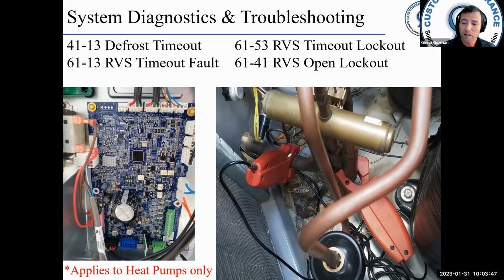Basically, you want to check the temperature difference across the valve, whether you're in cooling or heating. It's important to remember the single pipe on the reversing valve is always discharge, and the one in the middle of the 3 is always suction. What changes are the other 2 pipes. Whether you're in cooling or heating, you want to check the temperature difference across the valve. It's important for you to know what cycle you're in when you're taking the measurement. In most cases, you're going to want to have 2 clamps. Make sure the 2 clamps are accurate and that they read the same.